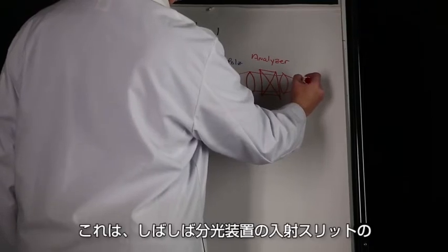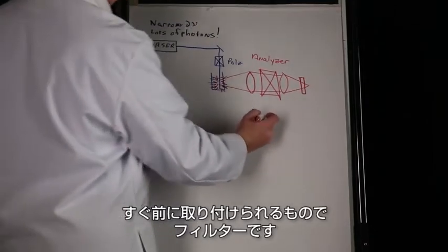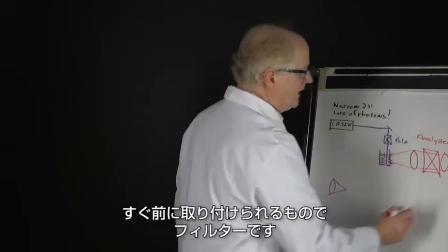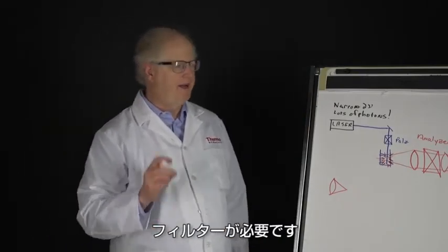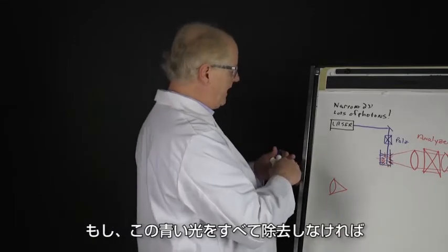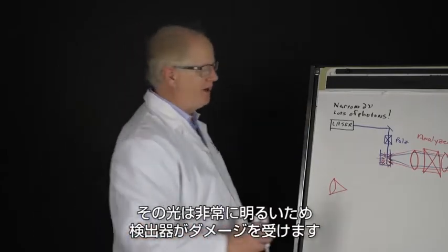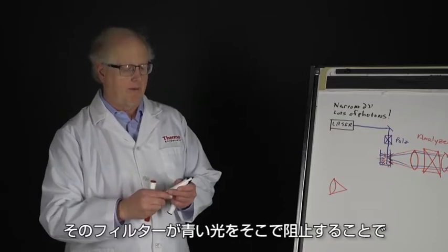The other thing that I'm going to put in there, and this is frequently put just right in front of the entrance slit of the spectrometer, is my filter. I have to have a filter, remember, to eliminate that Rayleigh light, because if I don't eliminate all of this blue light, all of that blue light if it got through to the detector would be so bright it would burn it up. But from this point on the only thing I'm going to get through is the red light. I'm going to be stopping that blue right there by that filter to protect my system.